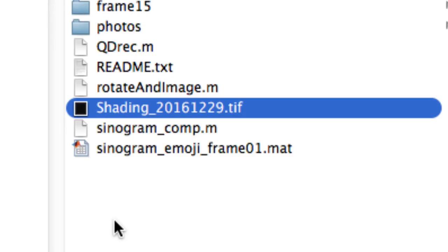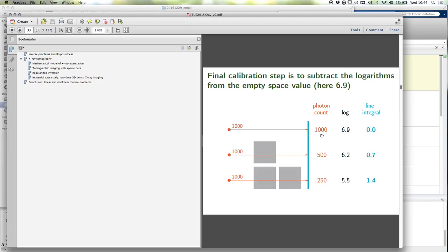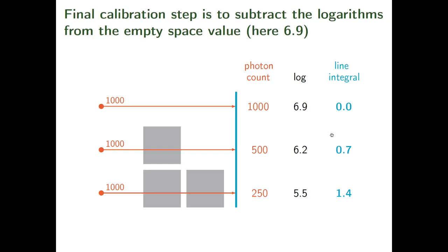This background image is also called dark field image sometimes. If there are no questions about that, we also have another image called shading — sometimes also called flat field. This is actually what we saw earlier measuring through empty space, because we need this empty space measurement to calibrate the measurements that go through the material.